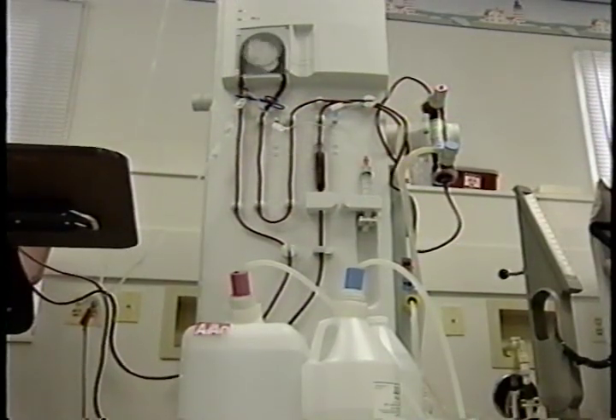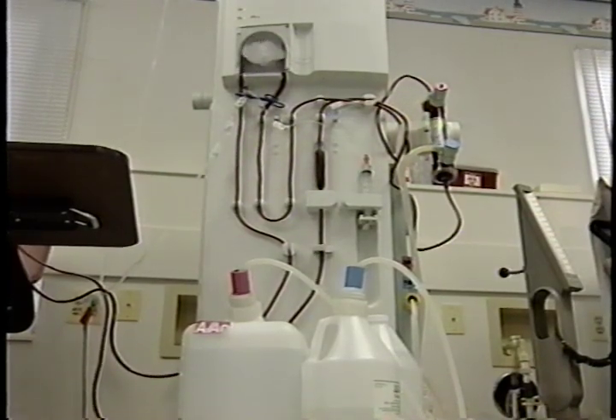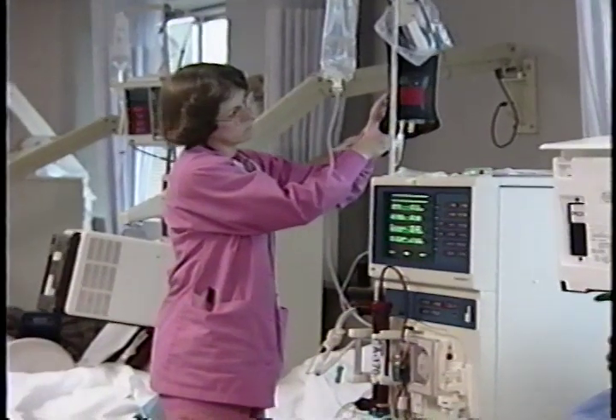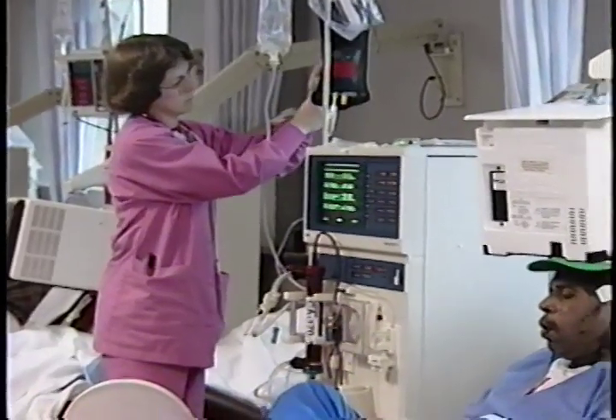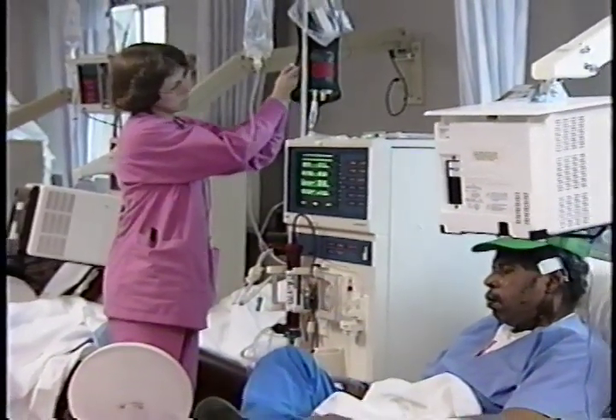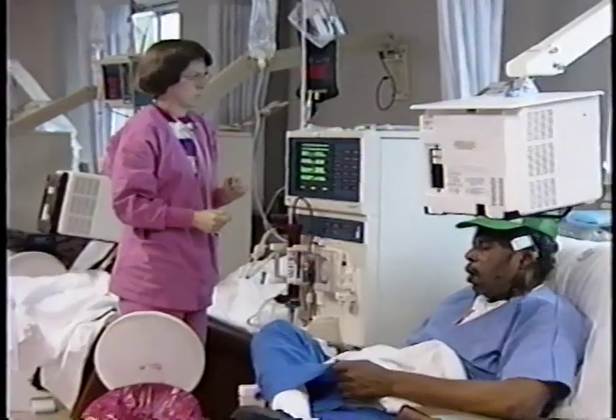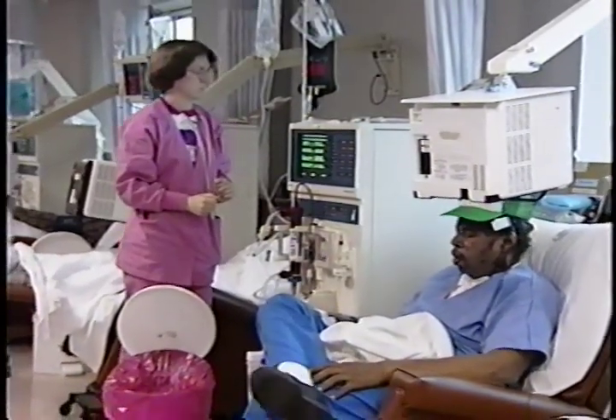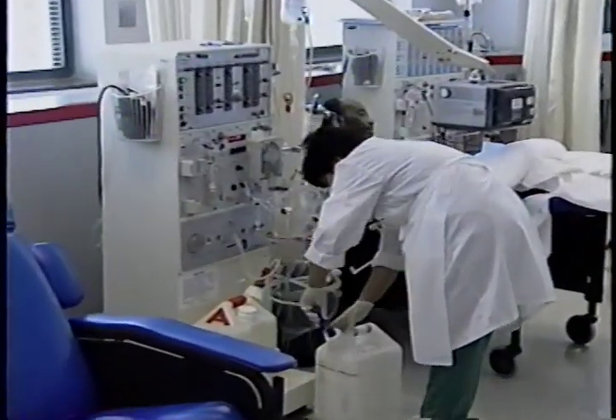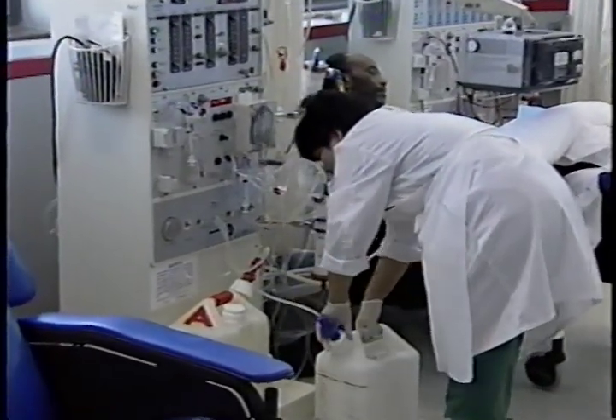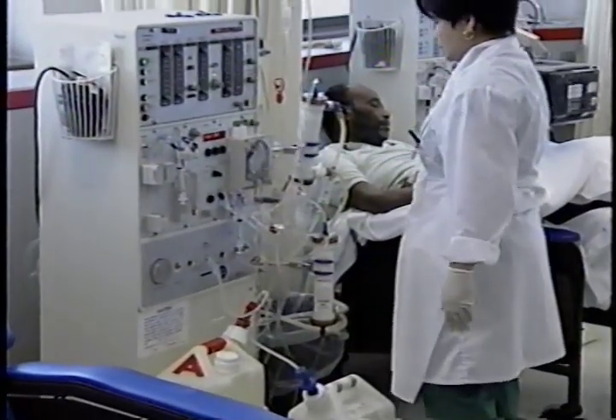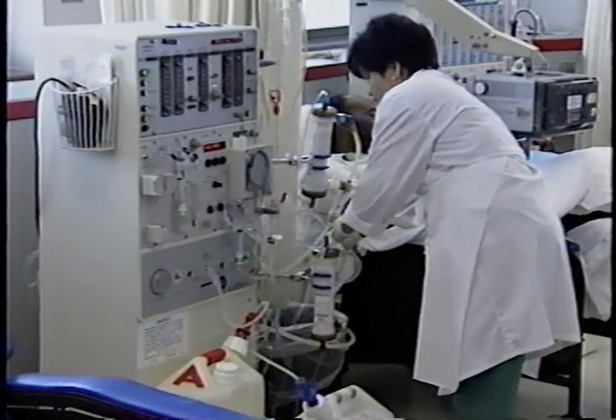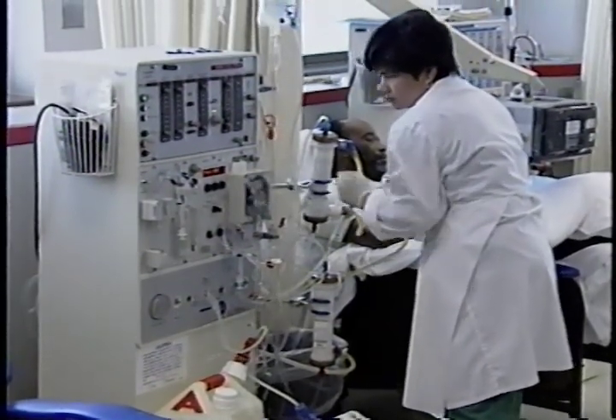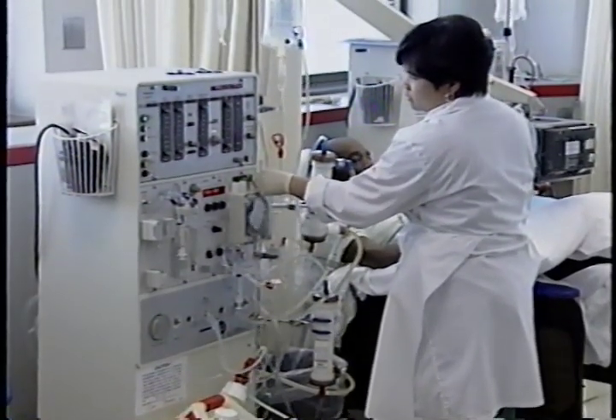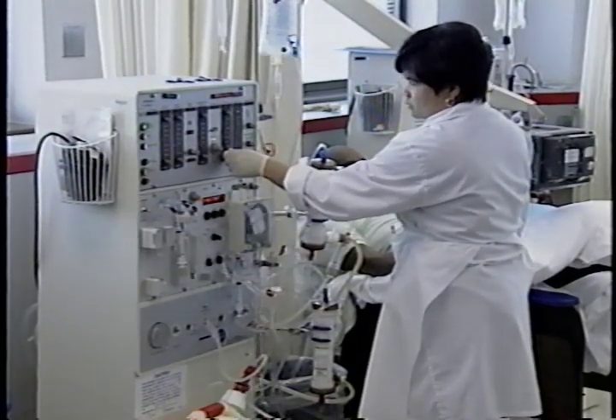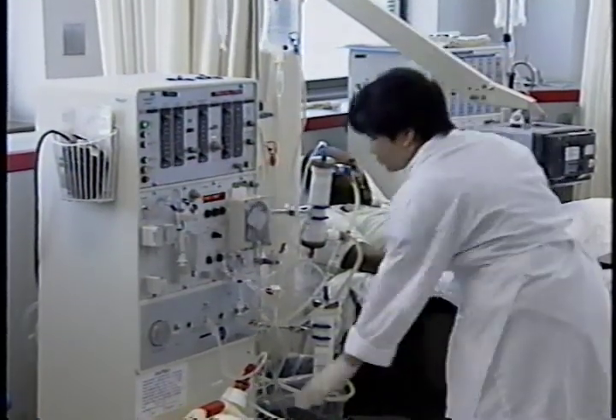Another important component of the dialysis prescription is the dialysate composition. The function of the dialysate is to balance the chemical composition of the body fluids. Failing to provide the prescribed dialysate can have serious adverse effects for the patient. First, you must assure that the prescribed formula and type of concentrate are used. It is essential that the acid component of bicarbonate dialysate concentrate not be confused with the acetate concentrate or with the bicarbonate concentrate. It is critical that you take the time to read the labels on these containers.